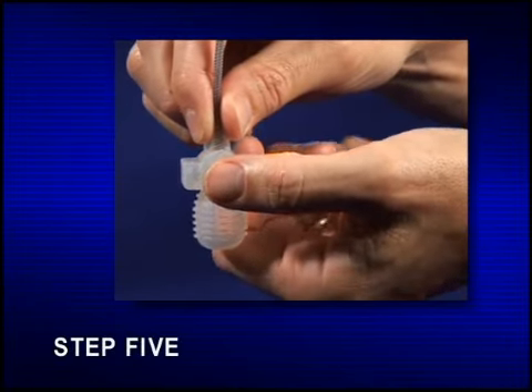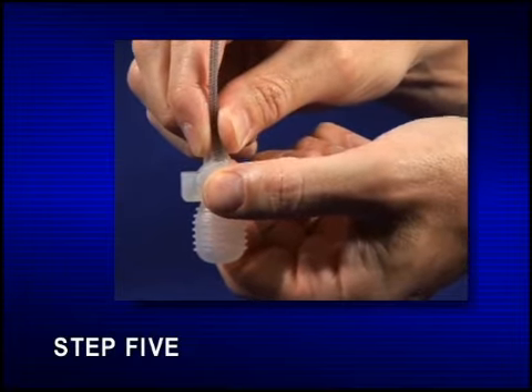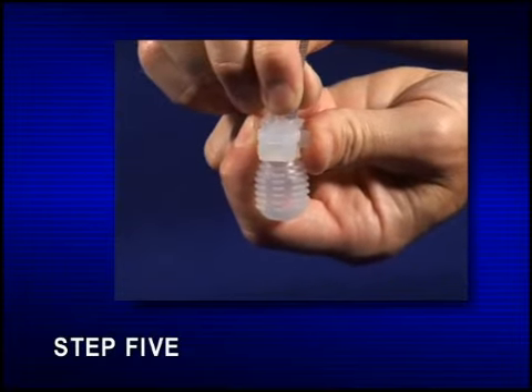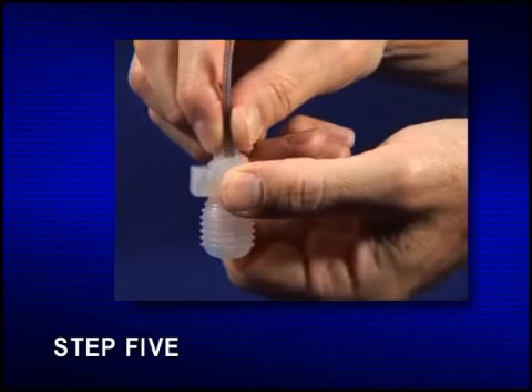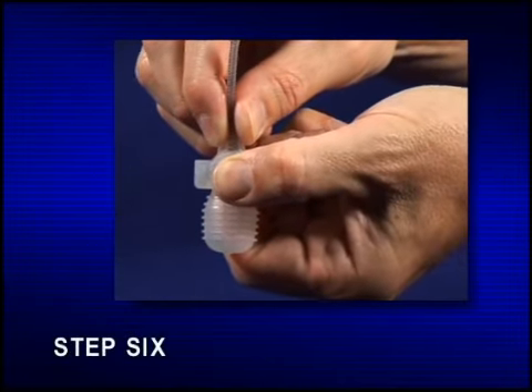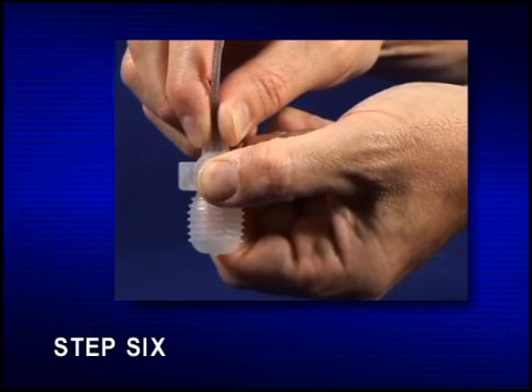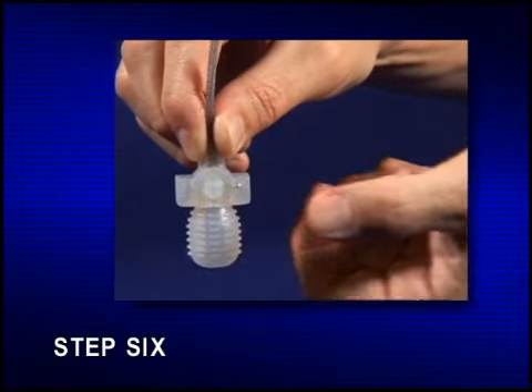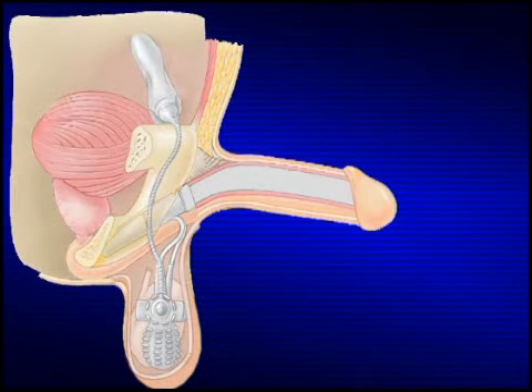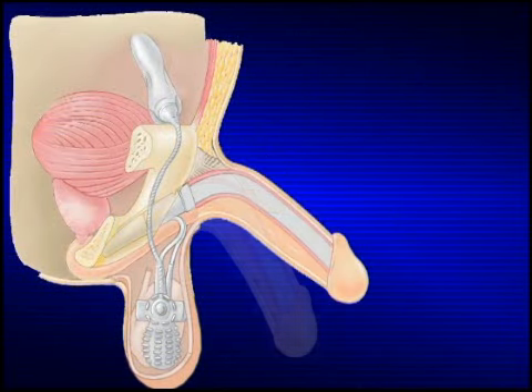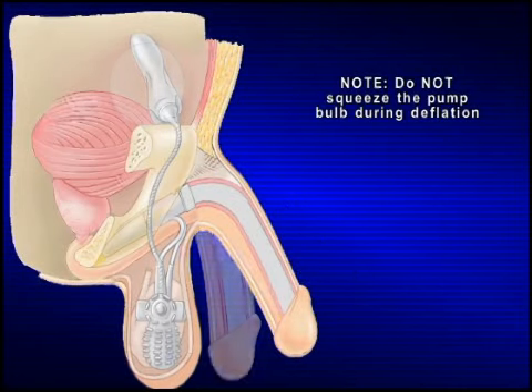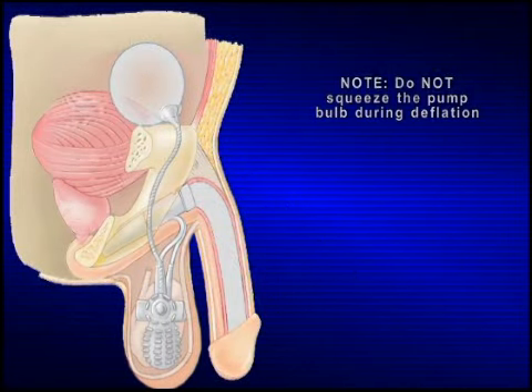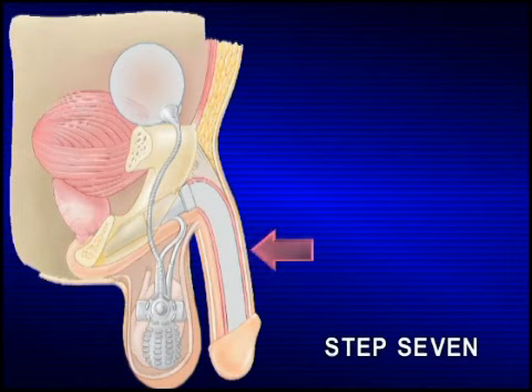Step 5. To effectively squeeze the deflation button, you must place a thumb and forefinger on opposite sides of the deflation block. Step 6. Squeeze the deflation button for about 4 seconds and then release. The cylinders will continue to deflate and the penis will become soft or flaccid. Note: do not squeeze the pump bulb during deflation. Step 7. After the cylinders have deflated, you may squeeze the penis to make it even more flaccid.